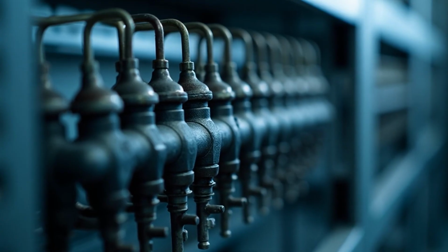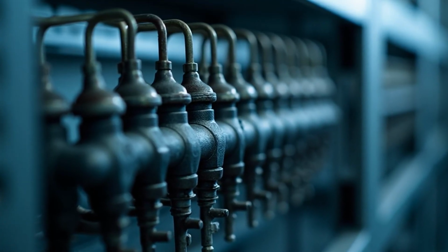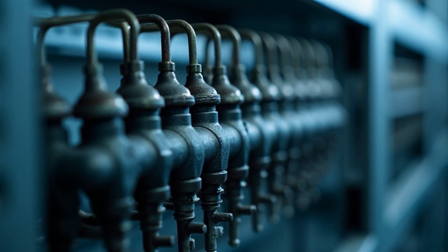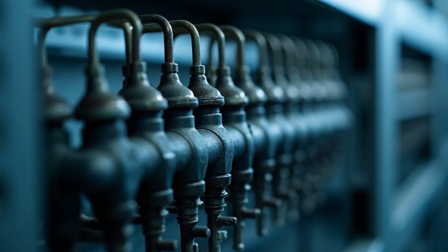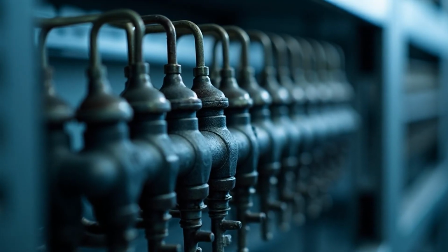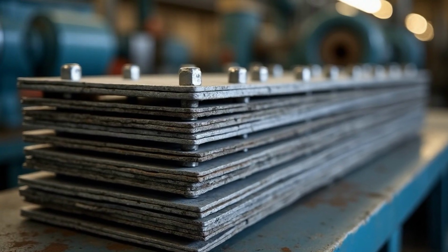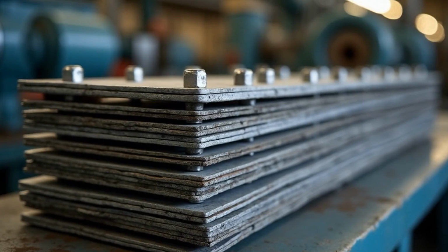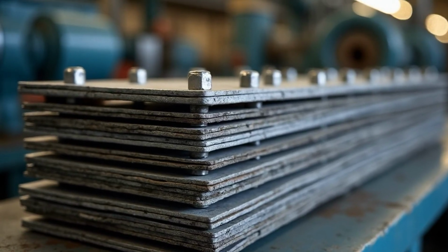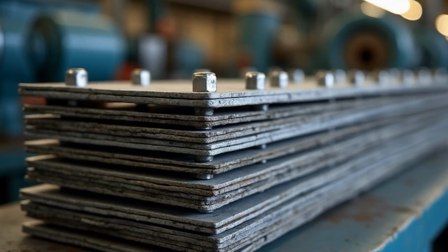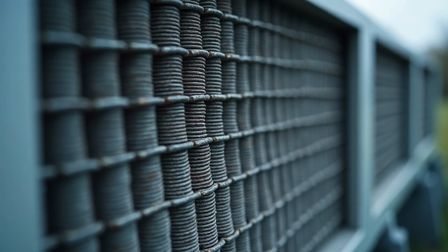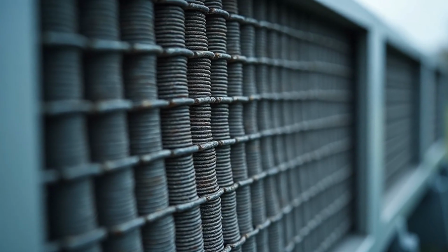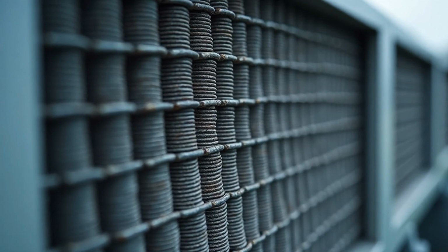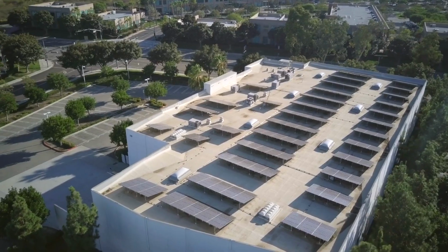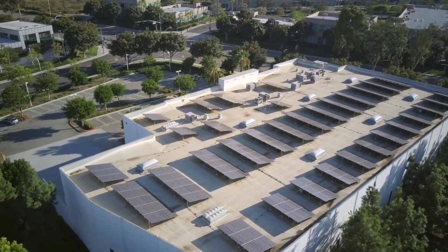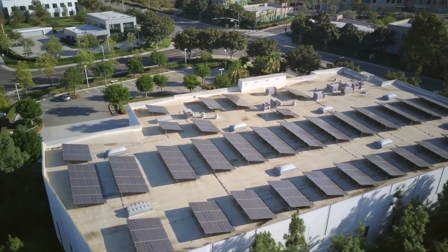There is a standard for this, and it is refreshingly blunt. Facility water classes W17, W27, W32, W40, W45, and W+. The number is the highest temperature of water you may send in. W32 means the equipment runs on water supplied at 32 degrees. That sounds minor. It is the whole economics of the building. If your chips demand cold water, you must manufacture cold, with chillers, machines that eat power all year. If your chips accept warm water, you can often skip that and cool the loop against outside air.